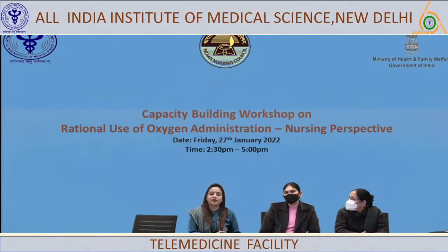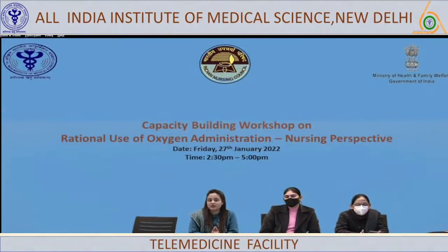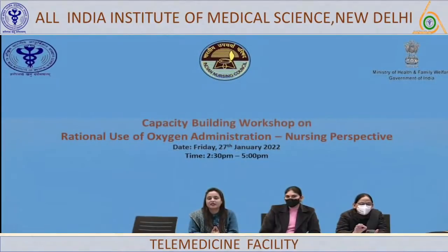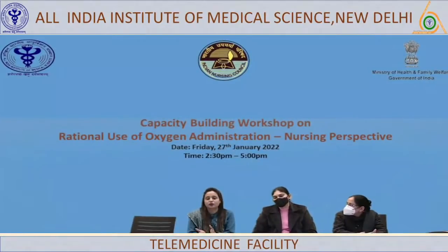So for that, you need to wash it up firstly with soap and detergent and rinse it with clean water. After rinsing it, dip it in 2% glutaraldehyde or Cidex solution for at least 30 minutes. Then we can take it out of the solution and rinse it with sterile water. So the main focus here is, after dipping in the solution, you need to rinse it with the sterile water, air dry it and keep it in a sterile drape until you need to use it again.